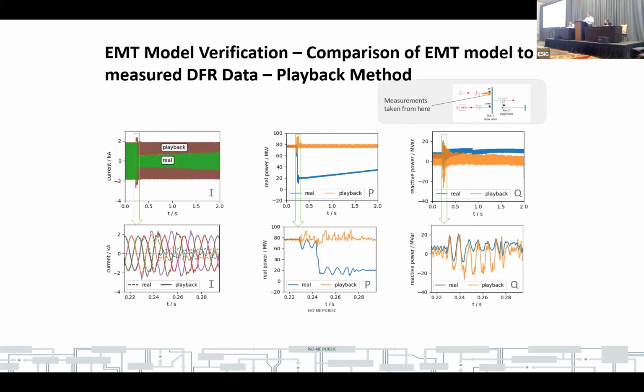But what the plant did was reduce very quickly down by 80% of its pre-disturbance output. So EMT model verification can be used in multiple ways: one, we can compare the actual response to the models, but also two, we can look for specific performance issues as well, as long as the models are accurate.